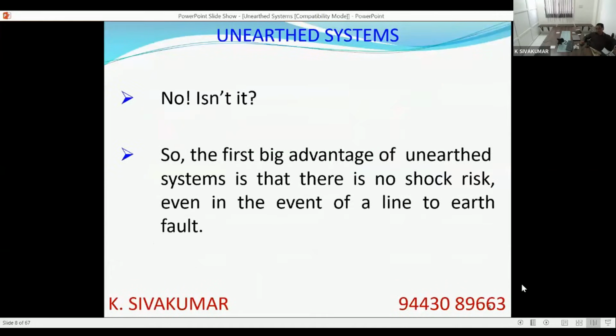So the first big advantage of an unearthed system is that there is no shock risk, even in the event of a line to earth fault, assuming that the capacitance is negligible. If the capacitances are significant, yes, the capacitive discharge may affect the person. But to simplify things, we will assume that negligible capacitance is there.